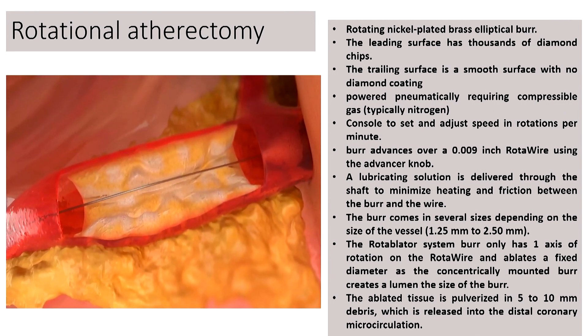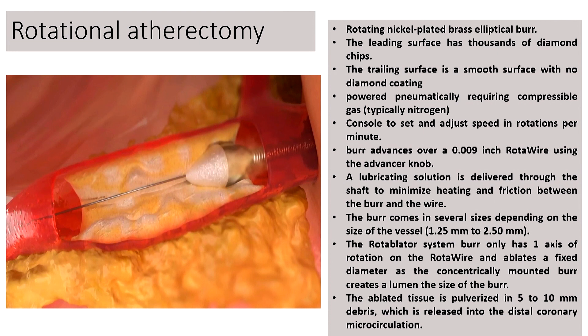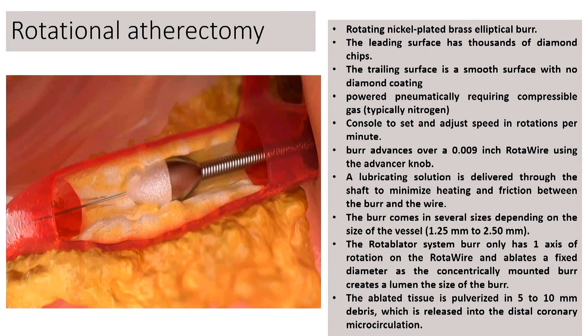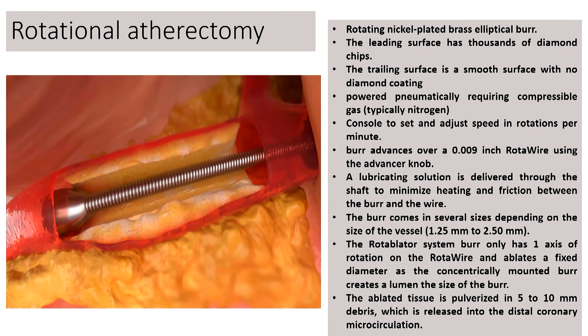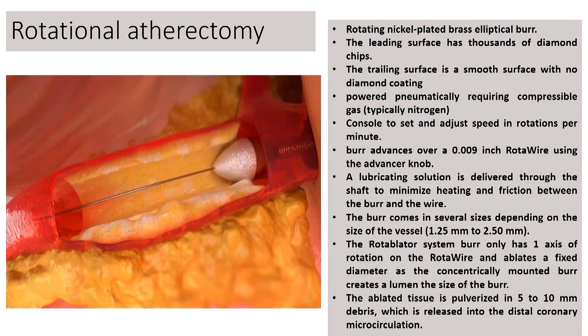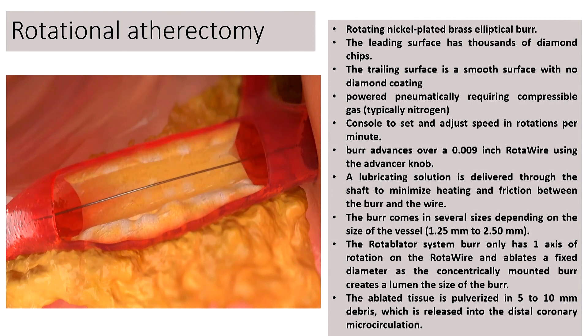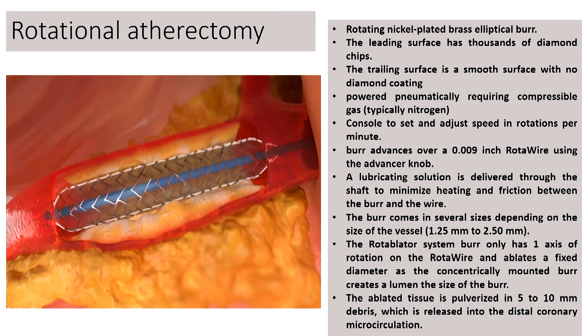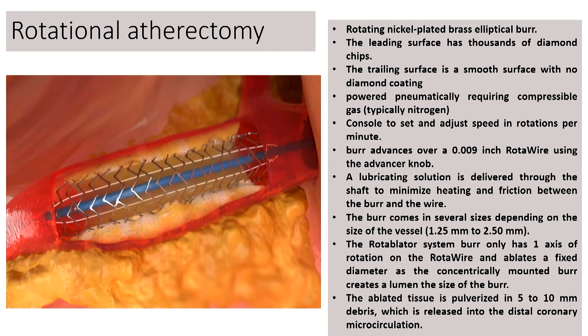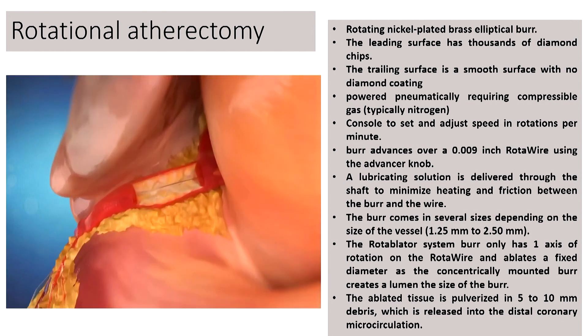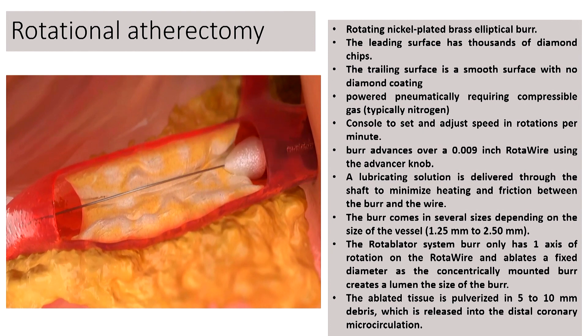Rotational atherectomy is a device with a rotating nickel-plated brass burr. It has a leading edge with thousands of diamond chips while the trailing surface is smooth. It is powered pneumatically using nitrogen gas and has a console to set and adjust the speed and rotations. It is advanced over a 0.009-inch wire using an advancer knob with a lubricating solution. The burr comes in sizes from 1.25 to 2.5 mm, and the burr-to-artery ratio should be 0.5 to 0.7 — for example, for a 3 mm vessel, choose a 1.5 mm burr. You should not oversize the burr. The system has one axis of rotation, ablating a fixed diameter, and ablated tissue is pulverized into 5 to 10 micron debris released into the distal coronary microcirculation.